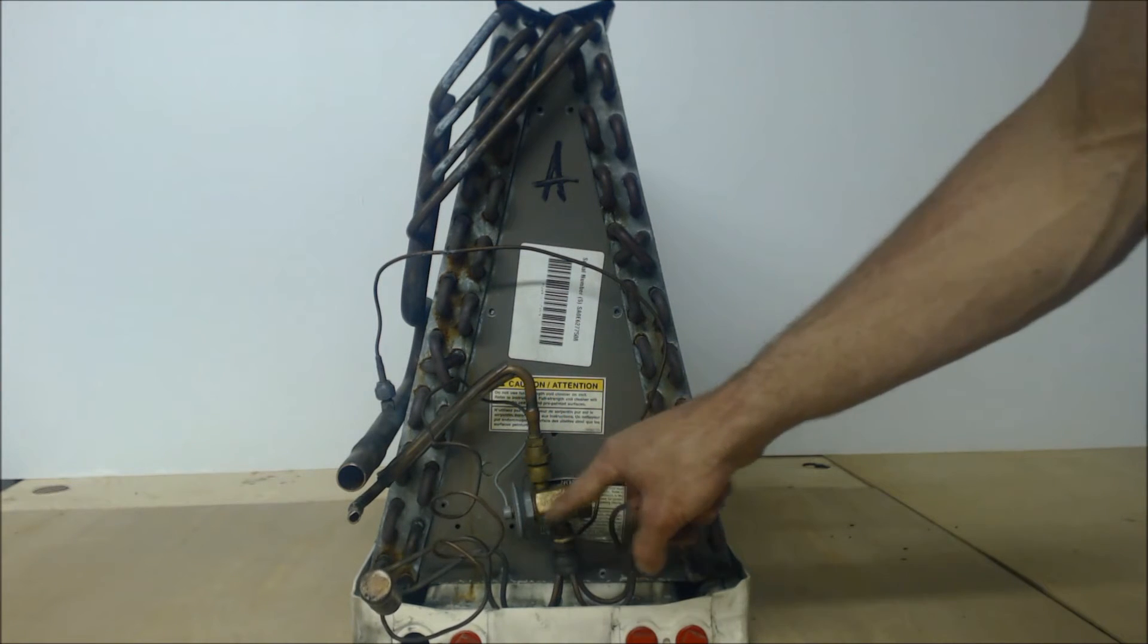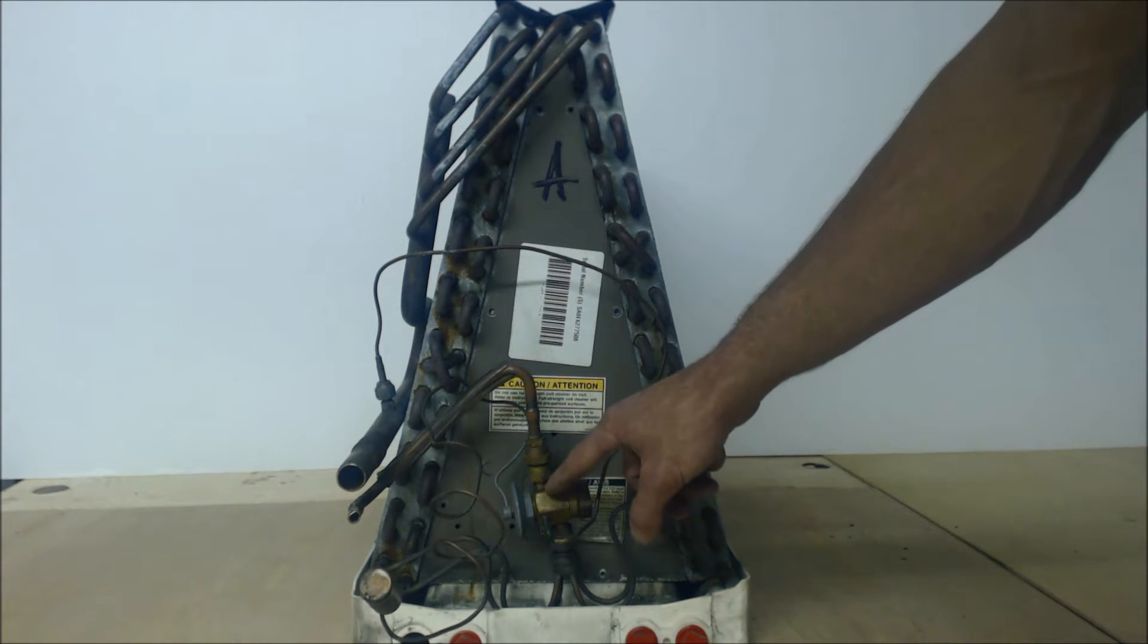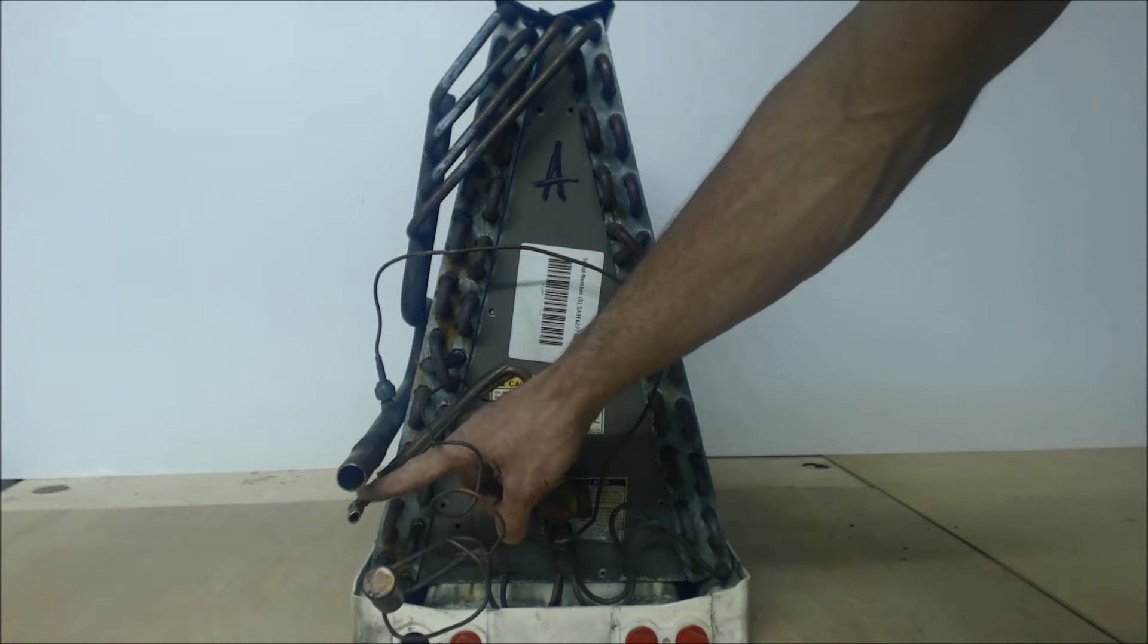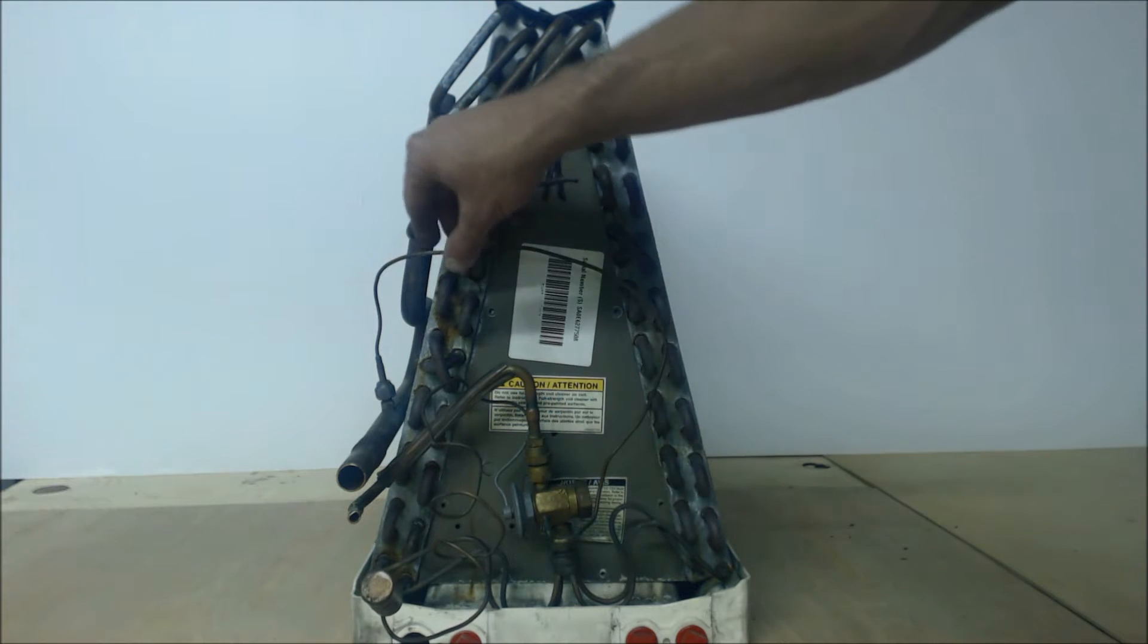You have several pressures coming into play here. You have the pressure coming in as liquid. Then you have this external equalization port, which is actually measuring the pressure on the suction line after the refrigerant goes through the evaporator coil.